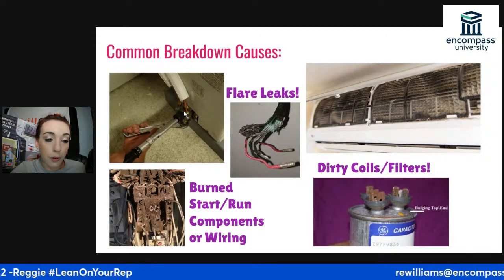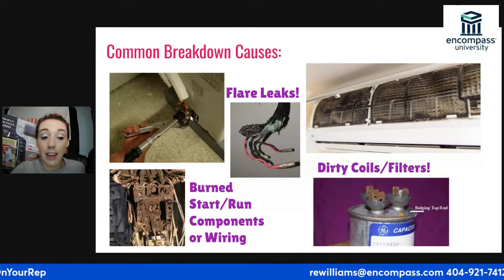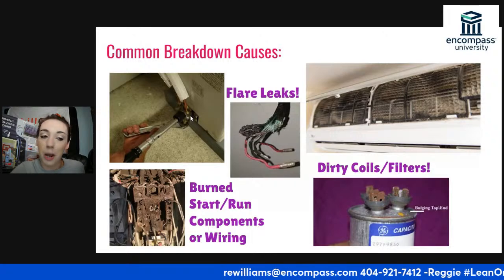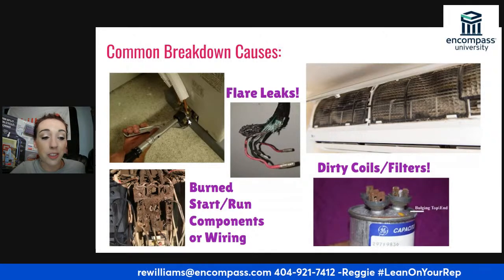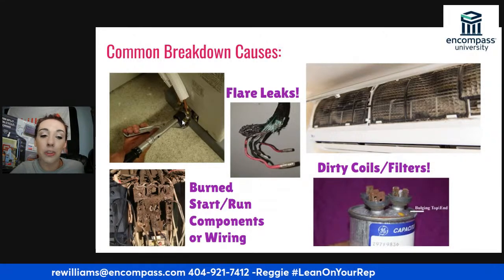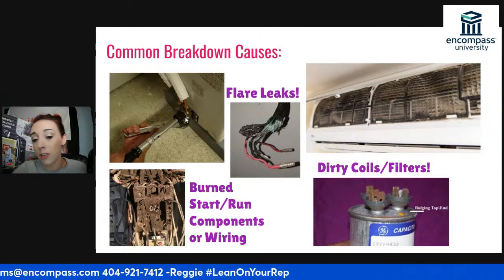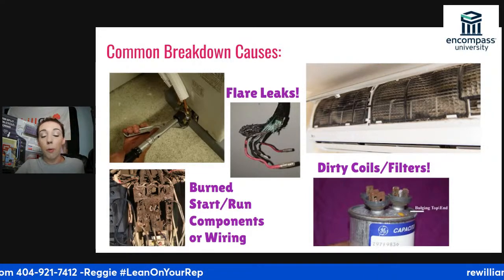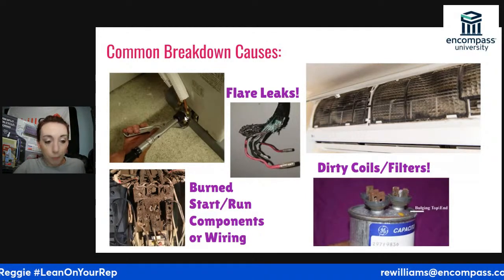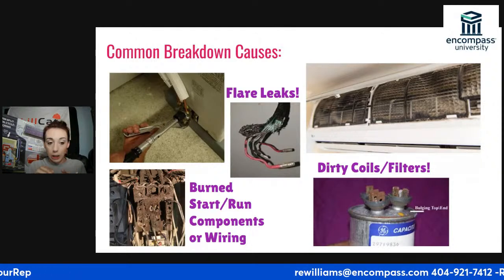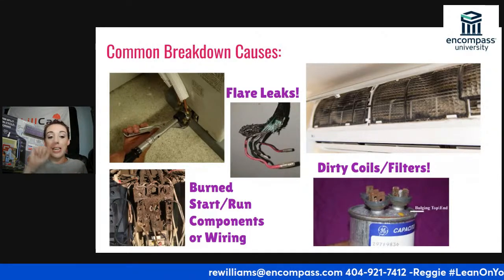A lot of people don't know that. They connect it as is. And after they have pulled a vacuum and they're done with their job and they go to startup, their system is empty because that was not a flare connection. That was just a squished piece of pipe. So what we have to do is use a flare tool to actually flare that so it's even on all sides.